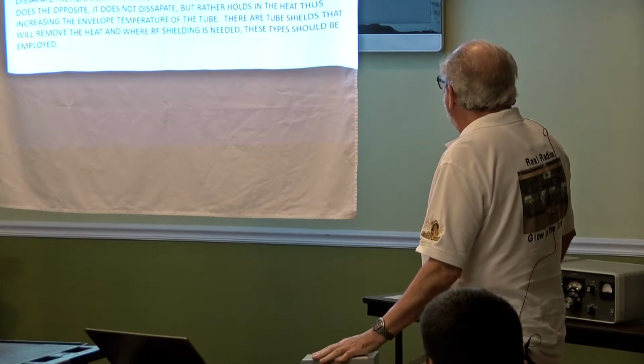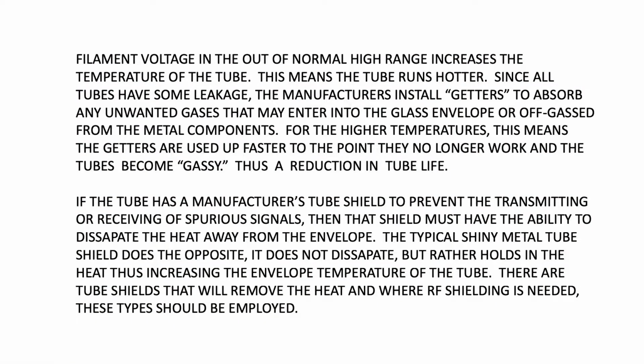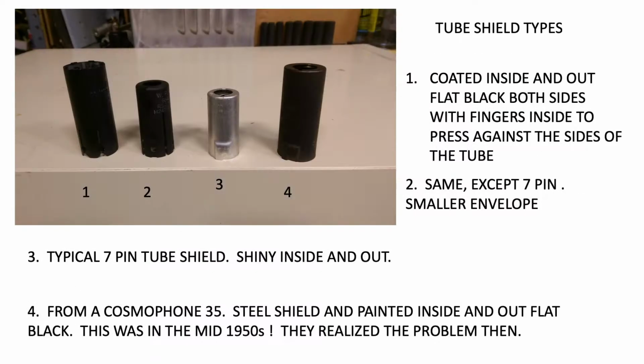The tube shields that will remove the heat and where RF shielding is needed, these types should be employed. So I'm going to give you a little lesson on that. Number 1, 2, 3, and 4. Number 1 is coated inside and out flat black with fingers inside to press against the sides of the tube. What are the fingers for? It's made out of metal. Metal is a very good conductor of heat, right? You take the temperature of the outside envelope of the glass, you physically touching it with metal, the metal conducts it to the outside perimeter of the shield. It's flat black, lovely black body radiator, and it radiates the heat, right?